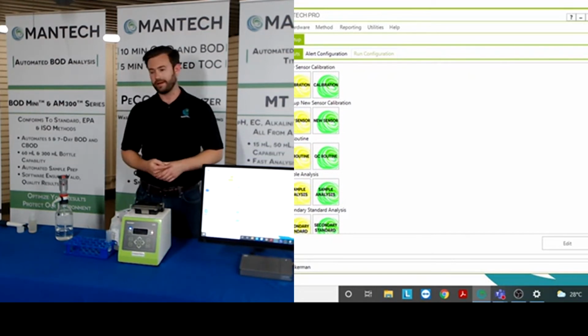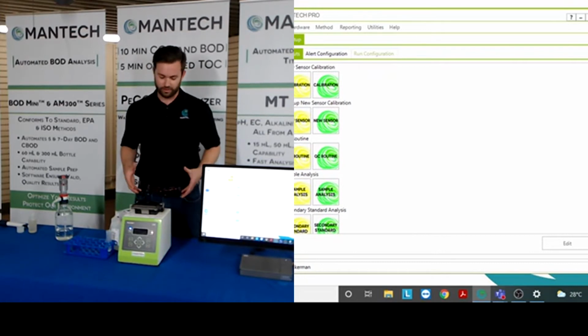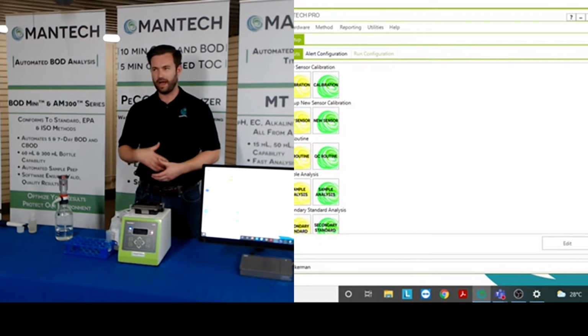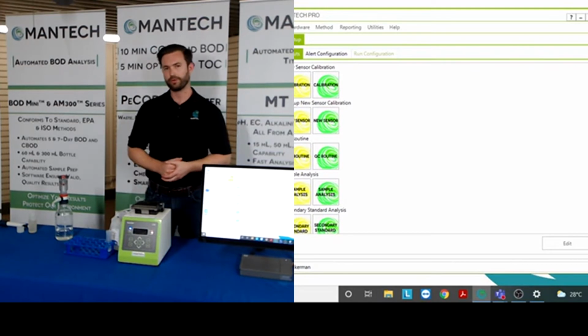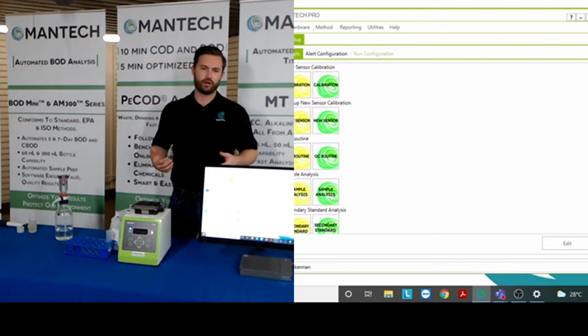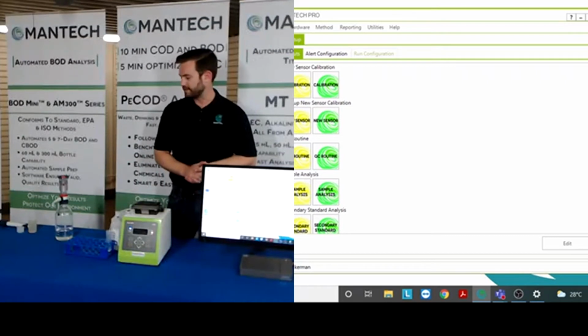Another automated feature is emails or text messages being sent directly to you, say after the PeCOD passes the calibration, after it's finished a sample, anything like that can just be sent right to you. And then there's also the automation of calibrations. So you can tell it the day before, all right, I'm going to be starting my PeCOD analysis at 7 o'clock in the morning. I need that to be ready at 7. So we're going to start the calibration at 6 or 5:30, and we're just going to let it go through, do its QC checks, and just be sitting ready for me to go when I get in at 7 o'clock in the morning. It's pretty nice.